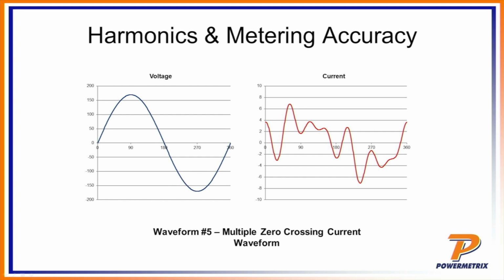Back in the day, a lot of meters were dependent upon that sinusoidal waveform for its fundamental clock, for its 60 hertz clock, which drove a lot of the digital electronics. And so some meters might use the voltage, some might use the current. The problem being that if I go from having a nice clean transition, meaning I'm generating a nice clean square wave at 60 hertz, to this waveform that's got all these zero crossings, that's going to generate a very confused looking clock. And so as such, the digital electronics of the meter might get confused to the point that it might give a very bad answer. And that was true. There for a while we had some meters that would get very confused by that.